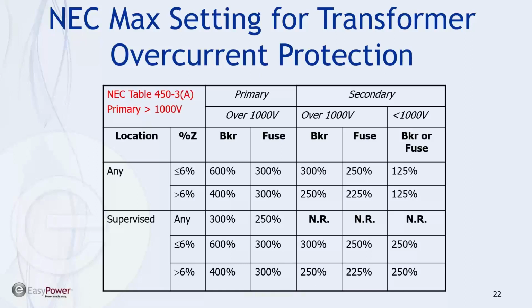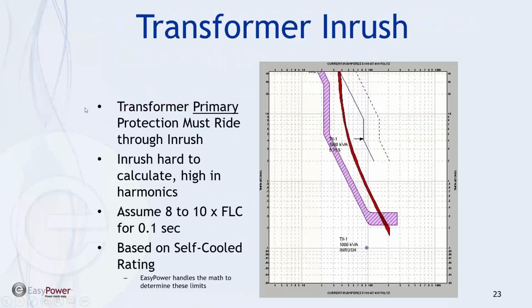On the primary side can be as high as 600% of full load current. And that doesn't mean it has to be, it just means at a maximum, that's where we want to set it. And when we get into coordination, this is something that will come into play. And again, this is part of the National Electrical Code.